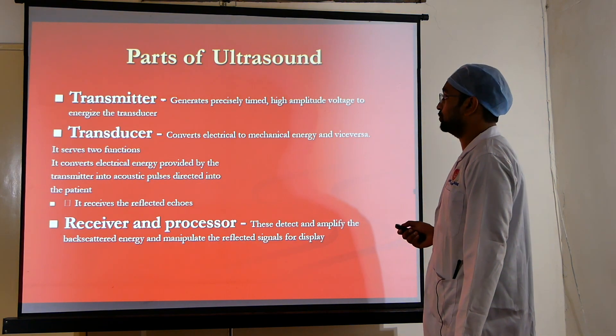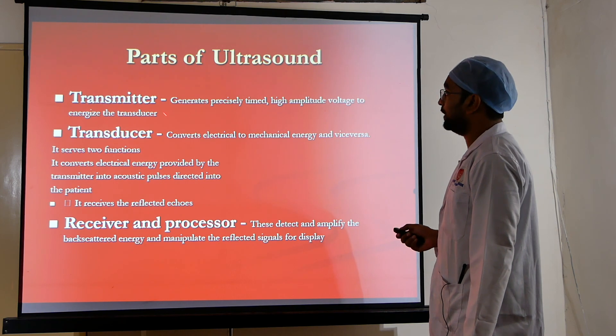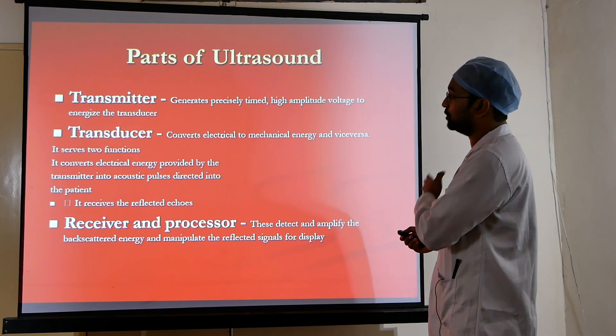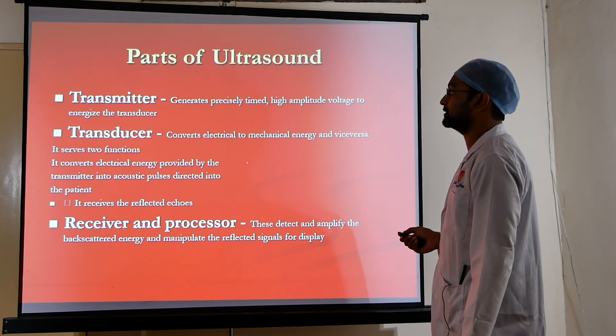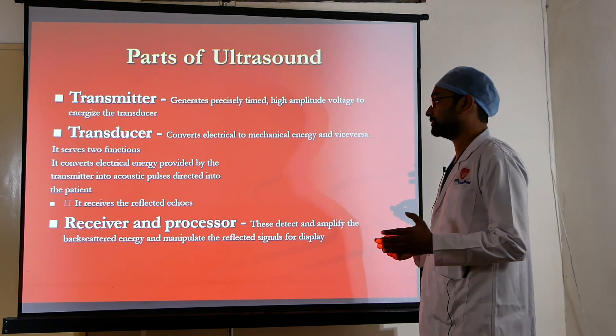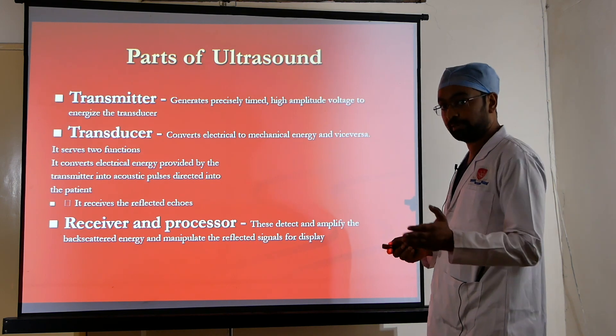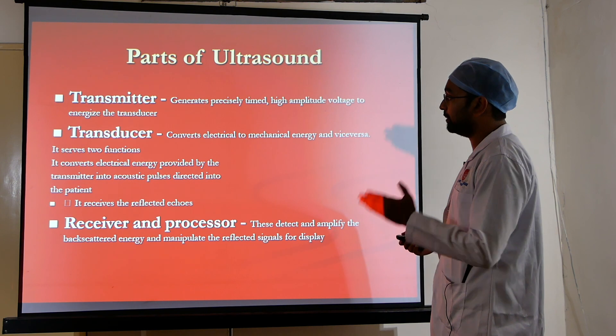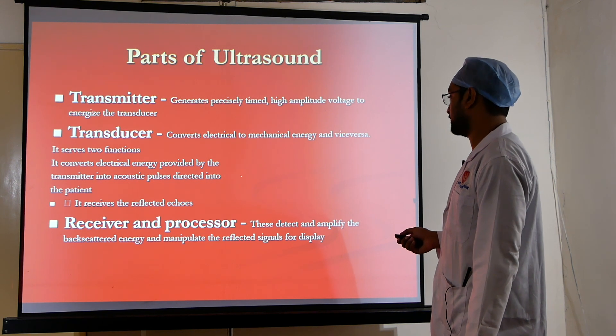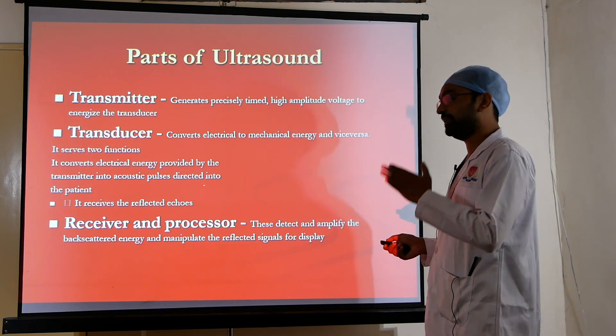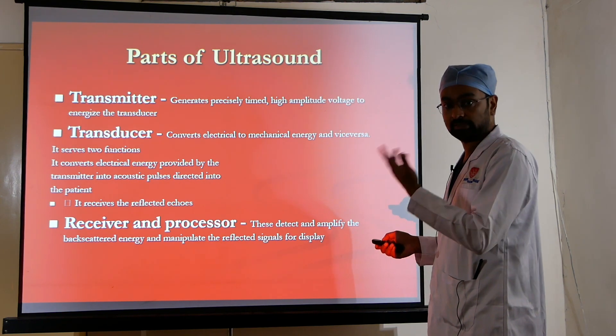The parts of an ultrasound machine: the transmitter generates precisely timed high amplitude voltage to energize the transducer. The transducer converts electrical energy to mechanical energy and vice versa — it converts electrical energy into acoustic pulses directed into the patient, and receives reflected echoes. The receiver and processor detect and amplify the back-scattered energy, manipulate the reflected signals, and produce the final ultrasound image.